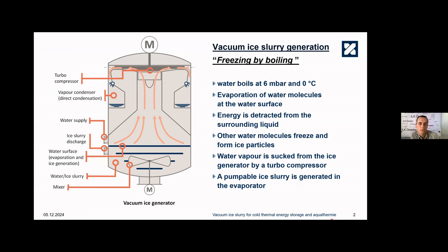You see here a vessel, and in the lower part of this vessel there is a water filling. Above the water you have water vapor, and this water vapor is sucked and compressed by a special turbo compressor to a higher pressure level. Then the water vapor is condensed again. By removing the water vapor from this space, evaporation of water takes place at the surface, and for this evaporation, heat is needed. This heat comes out of the water.